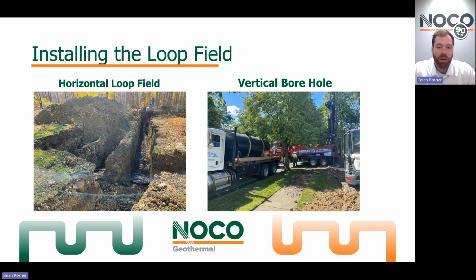But in that 500-foot deep hole, that's where your piping gets dropped in as a U of piping with a loop at the bottom. So it comes right back up. And then all the empty space between the pipe and the casing is filled with thermally conductive grout. All in all, that's a 6-inch wide, 500-foot deep heat exchange rod in the earth, essentially.